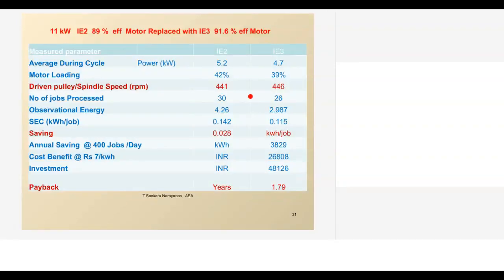So this is the advantage of doing a motor load survey. The auditor doing the motor load survey can find the existing load and where all the opportunities are. So this is a clear case for a high efficiency motor as well as resizing the motor. Being the first instance, the plant went for 11 kilowatt, because the 11 kilowatt drive was costing 48,000 rupees. Instead, if I had gone for 7.5 kilowatt, the investment also could have been less. Then 7.5 kilowatt loading would be better, and my further efficiency drop would be reduced. So wherever we do this energy efficiency motor replacement, we have to take care of all the existing parameters, then we should go. Suddenly somebody will say that after putting in the IE3 motor, my energy has increased. It can't increase if we monitor all the parameters clearly.